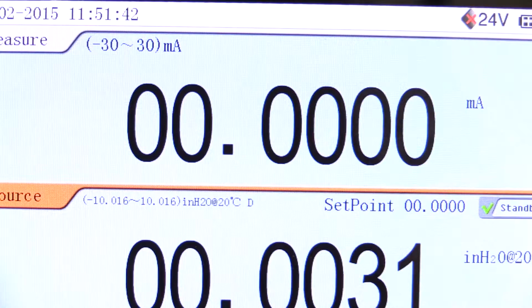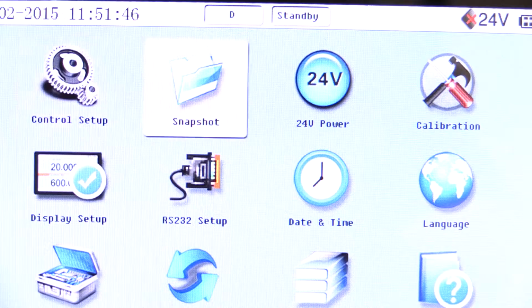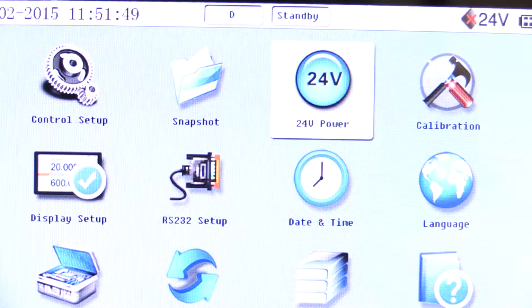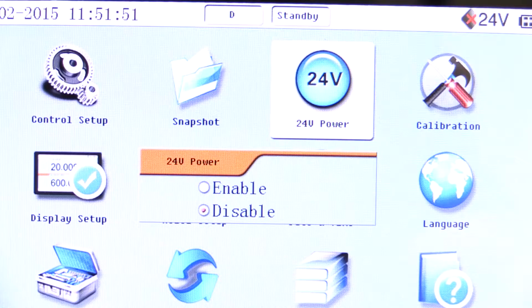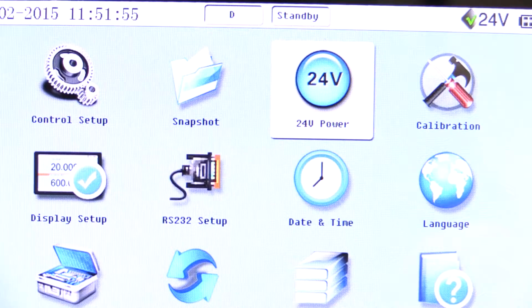By pressing Setup, we are able to select the 24-volt power function and enable or disable the internal supply of 24-volt loop power. In this case, we want the 24-volt loop power enabled.